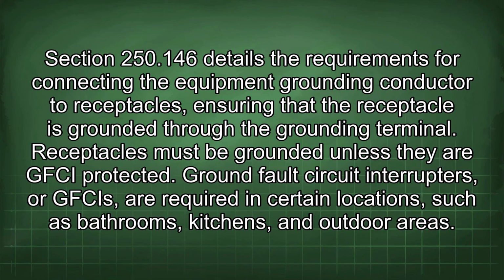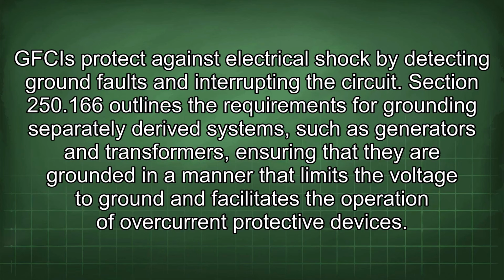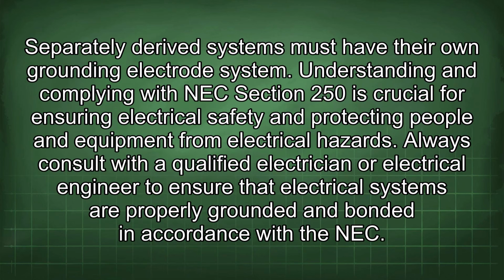Ground fault circuit interrupters, or GFCIs, are required in certain locations such as bathrooms, kitchens, and outdoor areas. GFCIs protect against electrical shock by detecting ground faults and interrupting the circuit. Section 250.166 outlines the requirements for grounding separately derived systems such as generators and transformers, ensuring that they are grounded in a manner that limits the voltage to ground and facilitates the operation of overcurrent protective devices. Separately derived systems must have their own grounding electrode system.